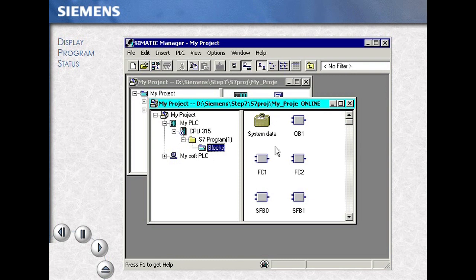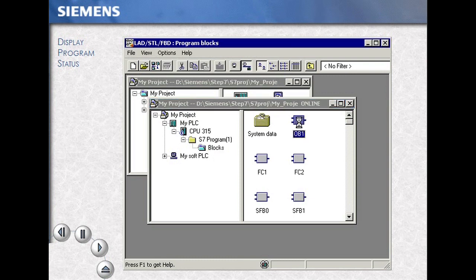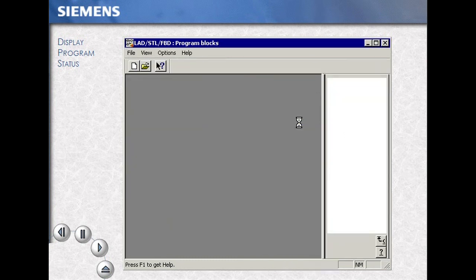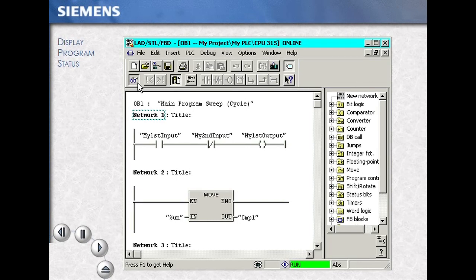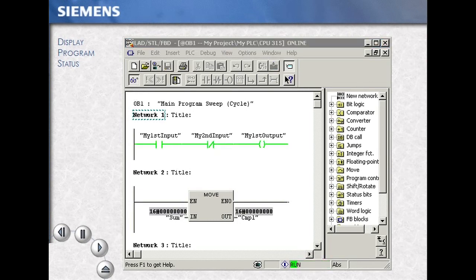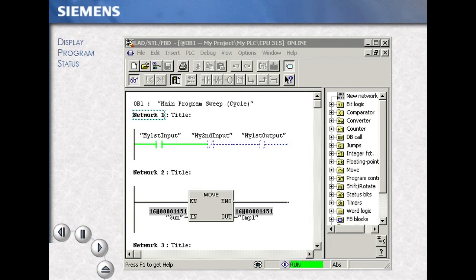When we double click on a code block to access the program editor, we now open the online block. Turning on the monitor or eyeglasses icon in the toolbar, we now see data updated from the PLC. Notice at the bottom of the screen that your run indication is on. Digital logic, analog logic, and other data are represented.